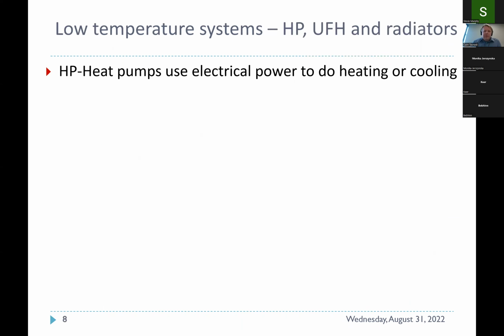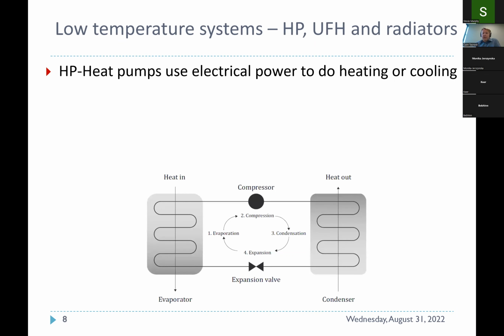Having a look now at low temperature systems with heat pumps, underfloor heating and radiators. If you're not familiar with heat pump technology, heat pumps just use electrical power to do heating and cooling. Here is a small diagram: we have heat in on one side, on the evaporator side, where the refrigerant goes from liquid to gas. By means of electrical power, we use a compressor, which compresses this gas, achieving higher temperatures. On this side is where we transfer that energy from the gas, from air let's say, to water. Therefore the name air to water, or ground source to water.